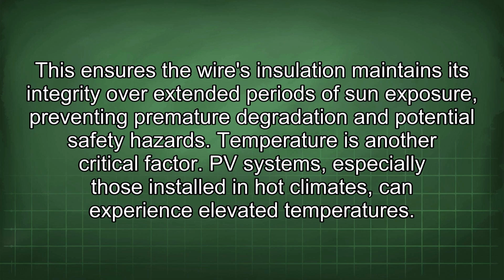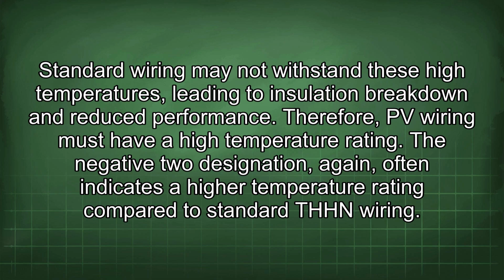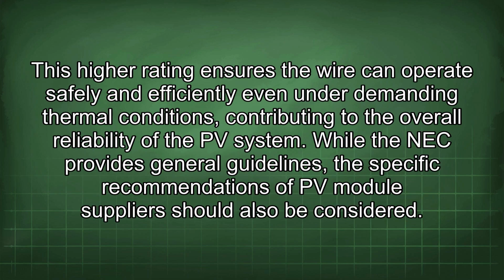Temperature is another critical factor. PV systems, especially those installed in hot climates, can experience elevated temperatures. Standard wiring may not withstand these high temperatures, leading to insulation breakdown and reduced performance. Therefore, PV wiring must have a high temperature rating. The -2 designation, again, often indicates a higher temperature rating compared to standard THHN wiring. This higher rating ensures the wire can operate safely and efficiently even under demanding thermal conditions, contributing to the overall reliability of the PV system.